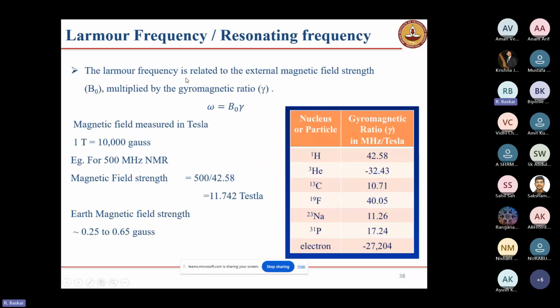The Larmor frequency is related to the external magnetic field strength multiplied by the gyromagnetic ratio of the particular nucleus. Omega equals B naught gamma. Here omega is the Larmor frequency or resonating frequency, B naught is the main magnetic field strength, and gamma is the gyromagnetic ratio. This is the table. This gamma is a constant for every nucleus; it is an intrinsic property of the individual nucleus. B naught we can change. When we increase B naught, the instrument frequency will increase.